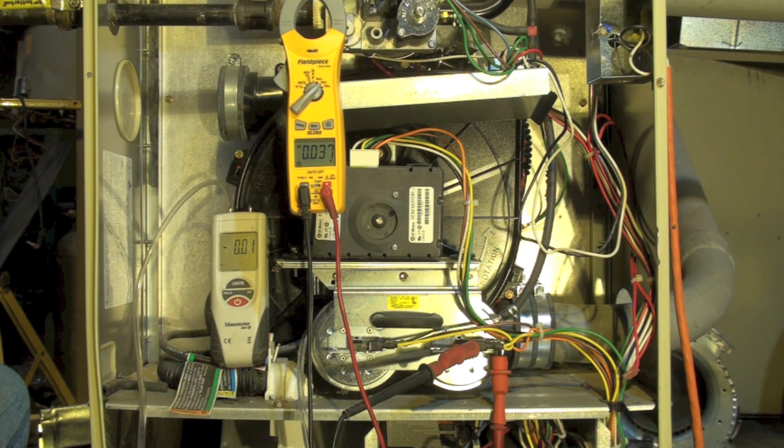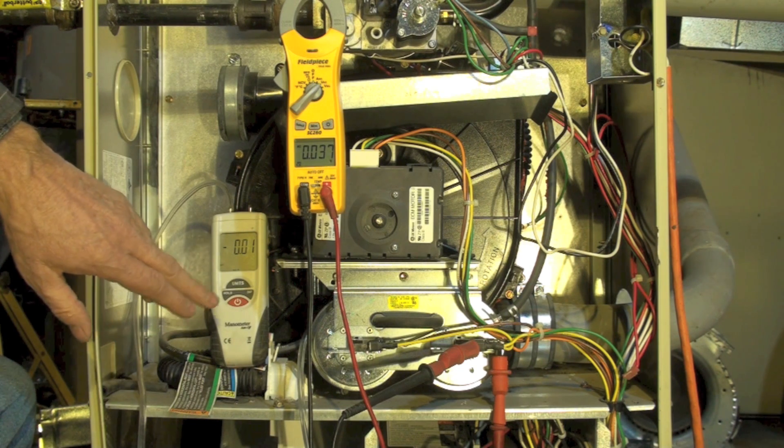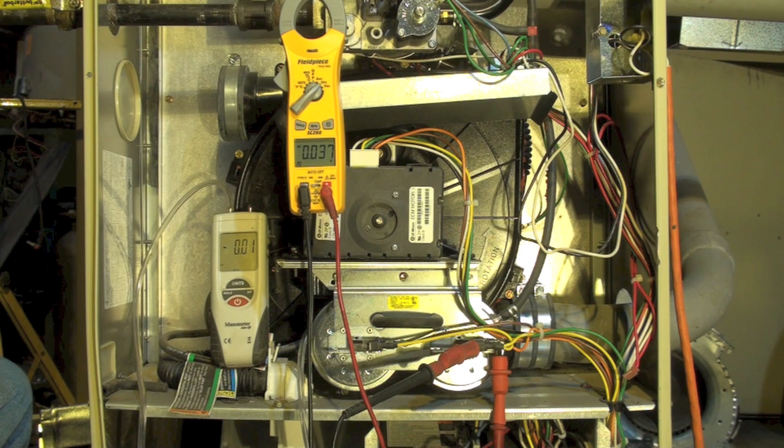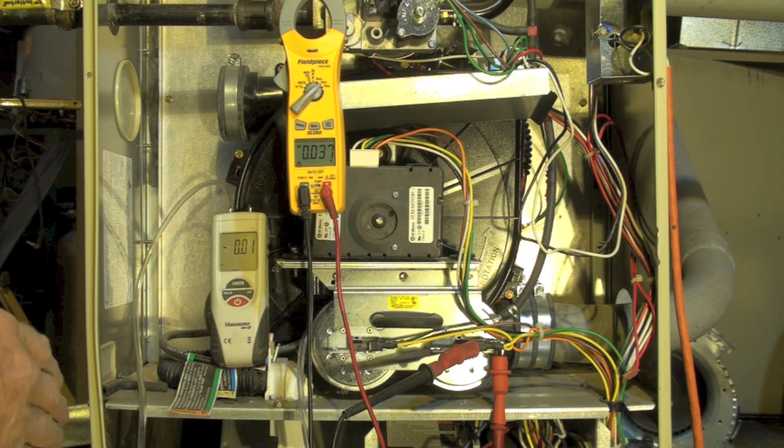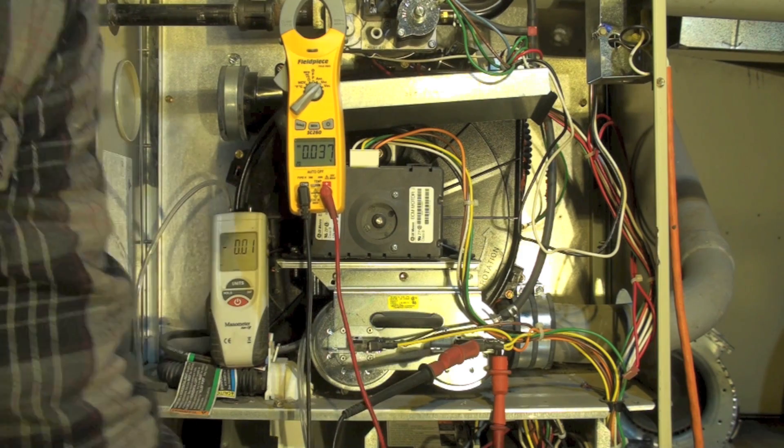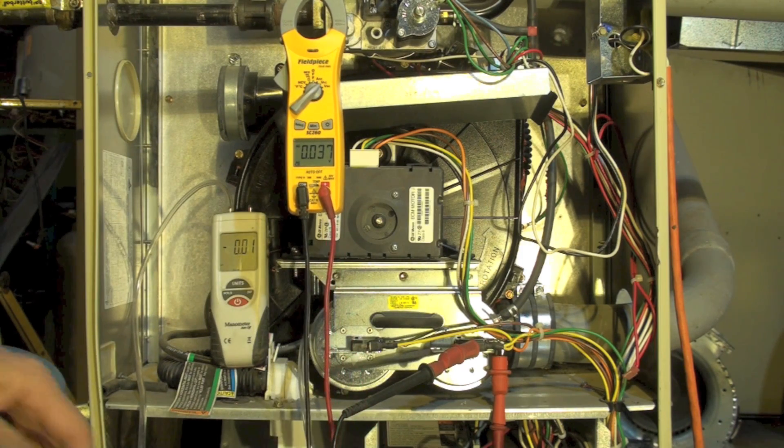And it's going to go up well above what it needs to make the pressure switch. You'll see the pressure go way up on this and you'll see that pressure switch close. And then once it lights, it's going to drop down. It's going to remember the speed it was when the pressure switch made and it's going to go back and be a little above that. So let's watch it work. You have to listen close to the inducer.